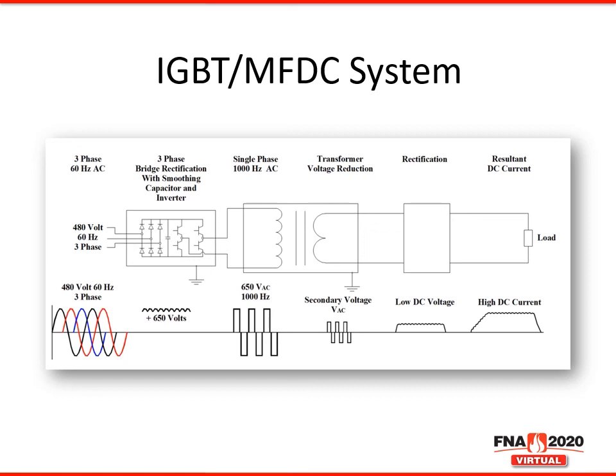Within the control, the power is first rectified into 650 volts single phase. It is then smoothed over with a capacitor and inverted with the IGBT into mid-frequency. The output of the control is 650 volts at 1000 Hz. This is distributed to the MFDC transformer and stepped down to low voltage, high current power. Within the MFDC transformer, there are diodes that then rectify the mid-frequency AC waveform into high amperage direct current output. This DC current is then delivered to the load or whatever heating process you are using.